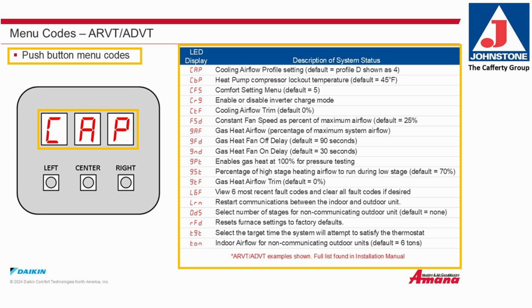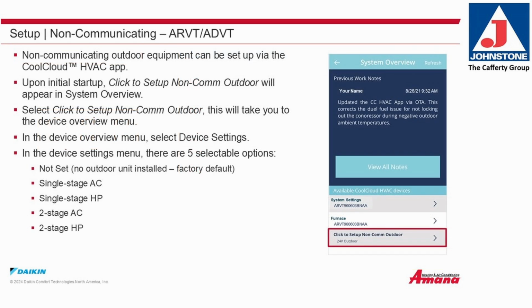Setup for a non-communicating outdoor unit and the ARVT, ADVT furnace. Non-communicating outdoor equipment can be set up via the CoolCloud HVAC app. On initial startup, click to set up non-com outdoor will appear in the system overview. Select Click to set up non-com outdoor. This will take you to the device overview menu. In the device overview menu, select device settings.